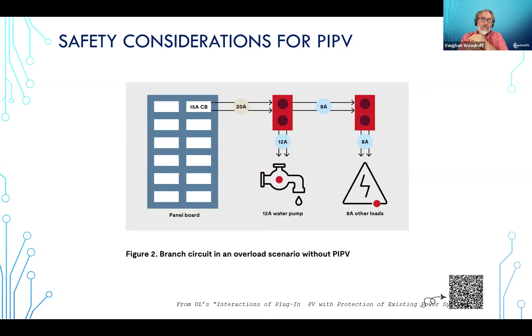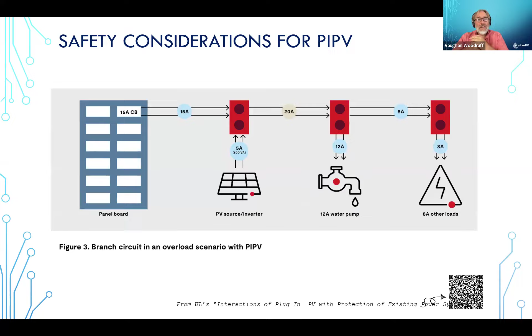And this is the instance that Stephan showed. If that PV source is between the circuit breaker and the load, you can see that 20 amps on those wires would exceed what's there without the breaker opening. So these are some of the considerations that folks are trying to figure out.